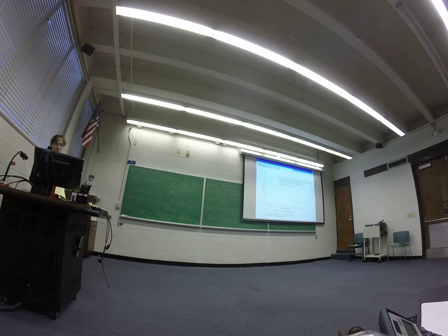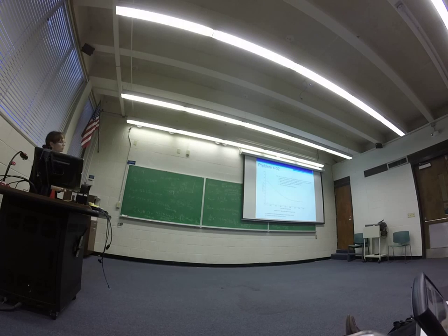So that's just a matter of reading from the chart, right? When did it start? Kind of hard to see unless you actually have a straight line that you can put through here. So obviously the leak starts here because this is when it starts to go down. Okay, it's about 100 minutes. Okay, how long did it last? Roughly.